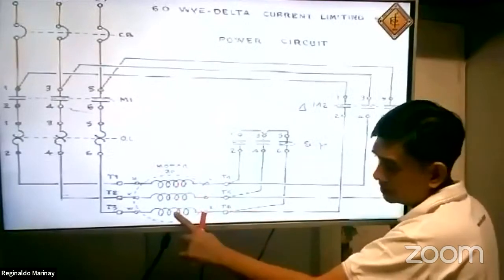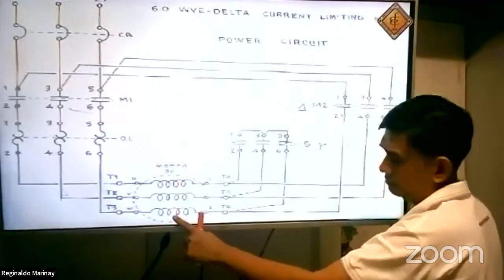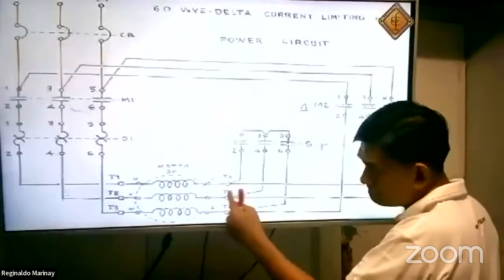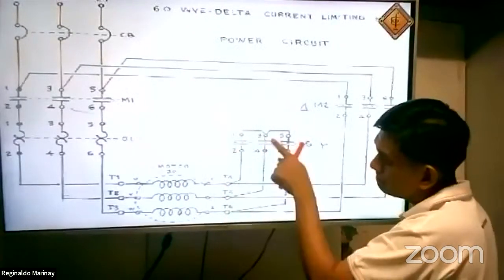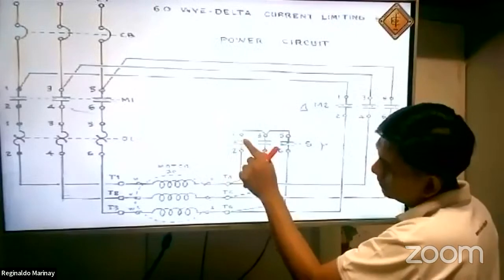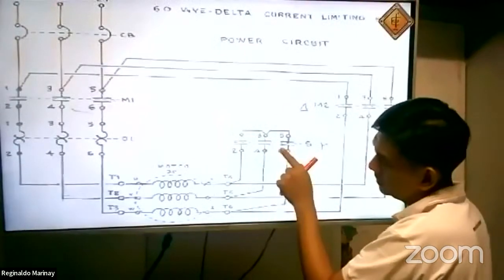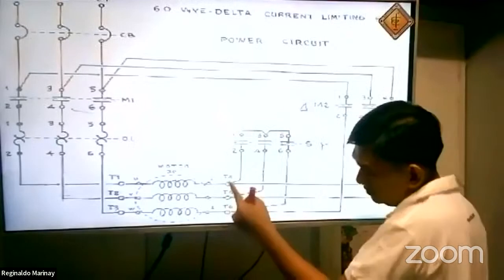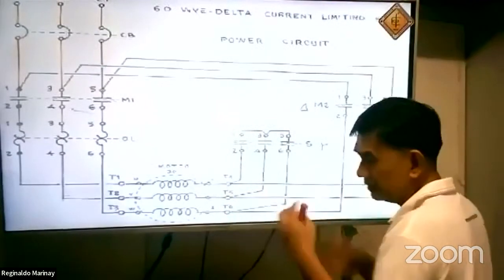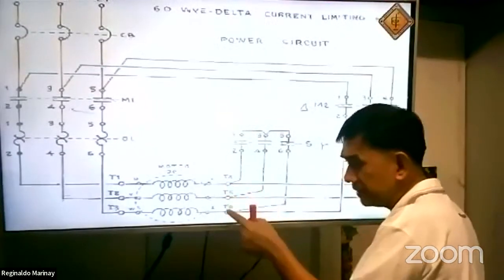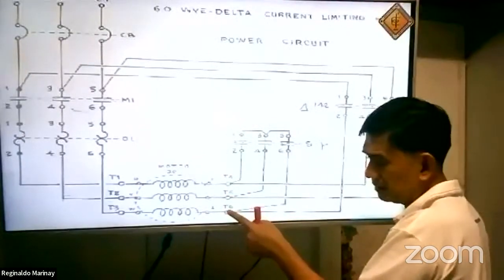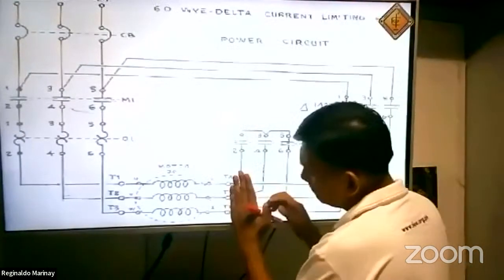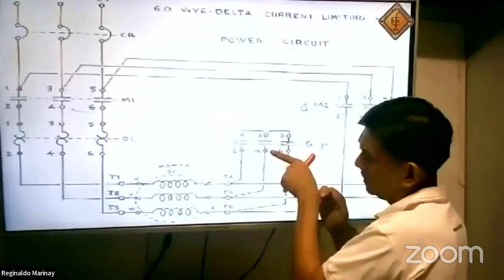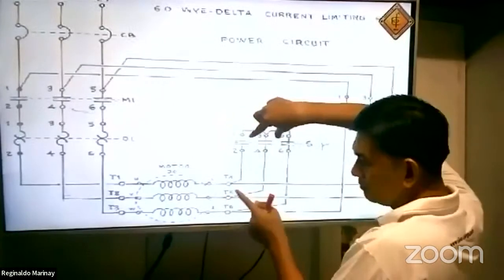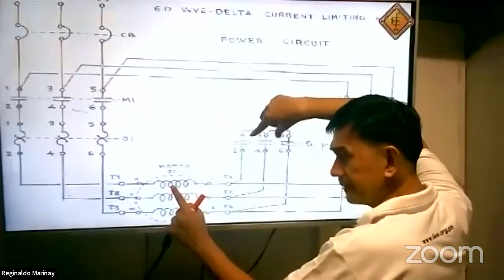There is a winding here. There's a certain resistance or impedance here. Once you short this, it's like saying that this becomes short-circuited. It seems like T4, T5, and T6 of the motor are short-circuited, but they're not. Once you close these 3, this simply proves that these 3 coils are connected in Y.